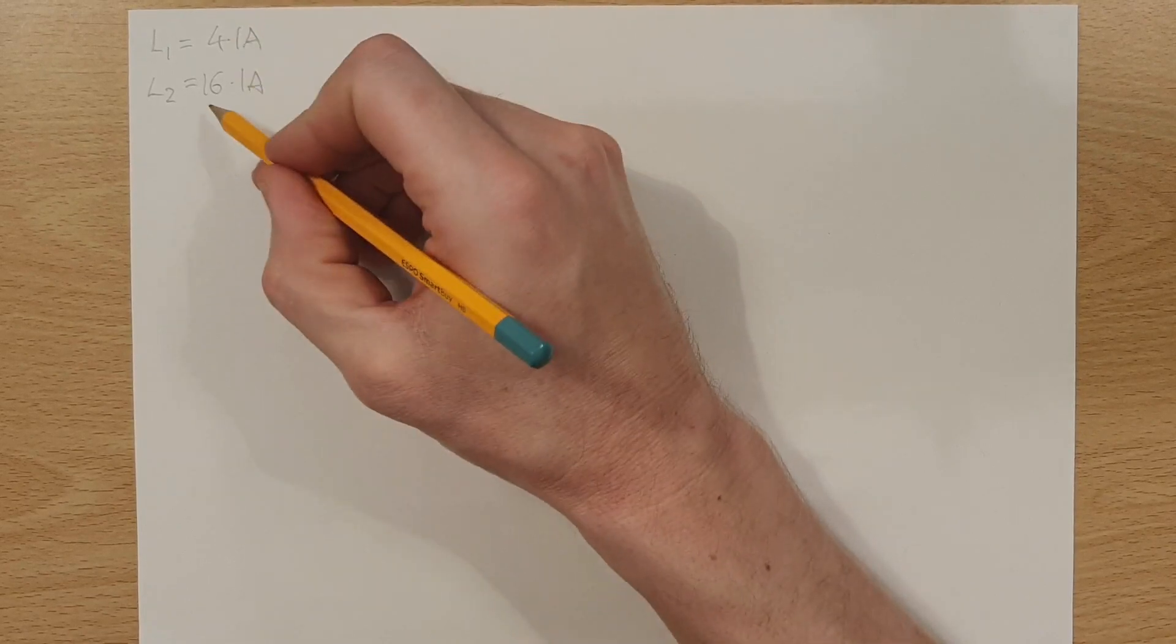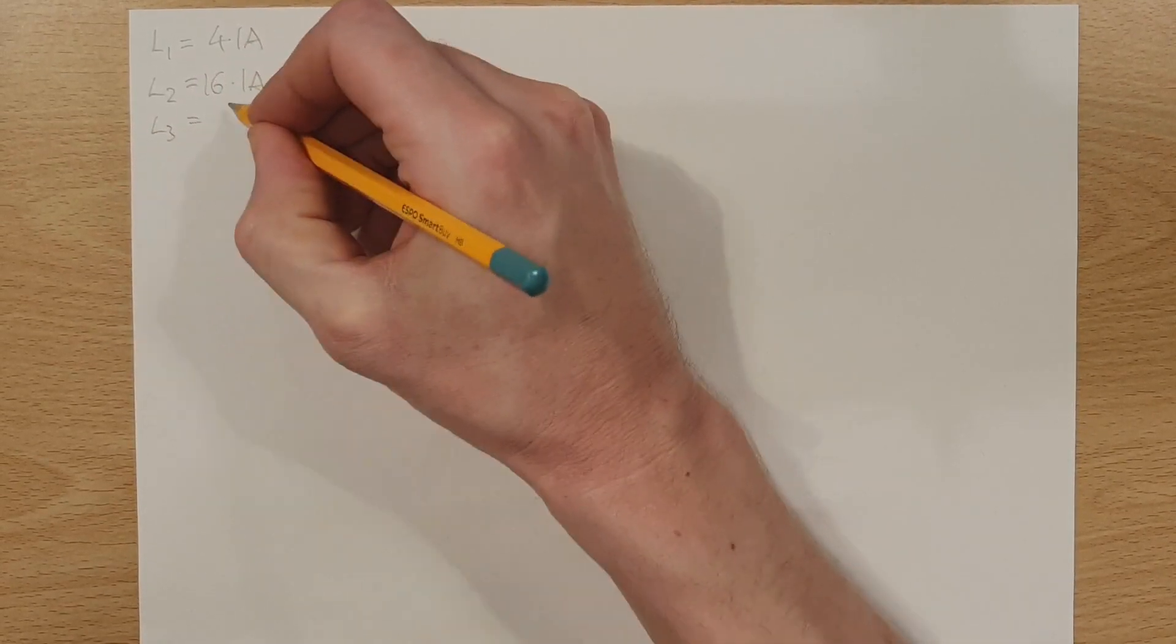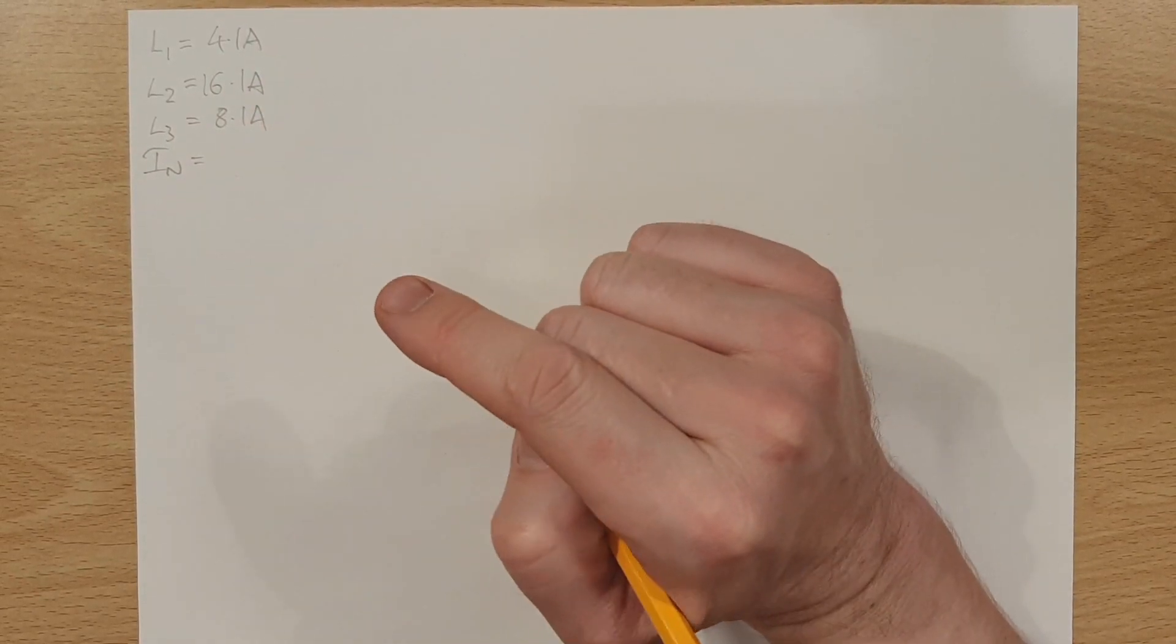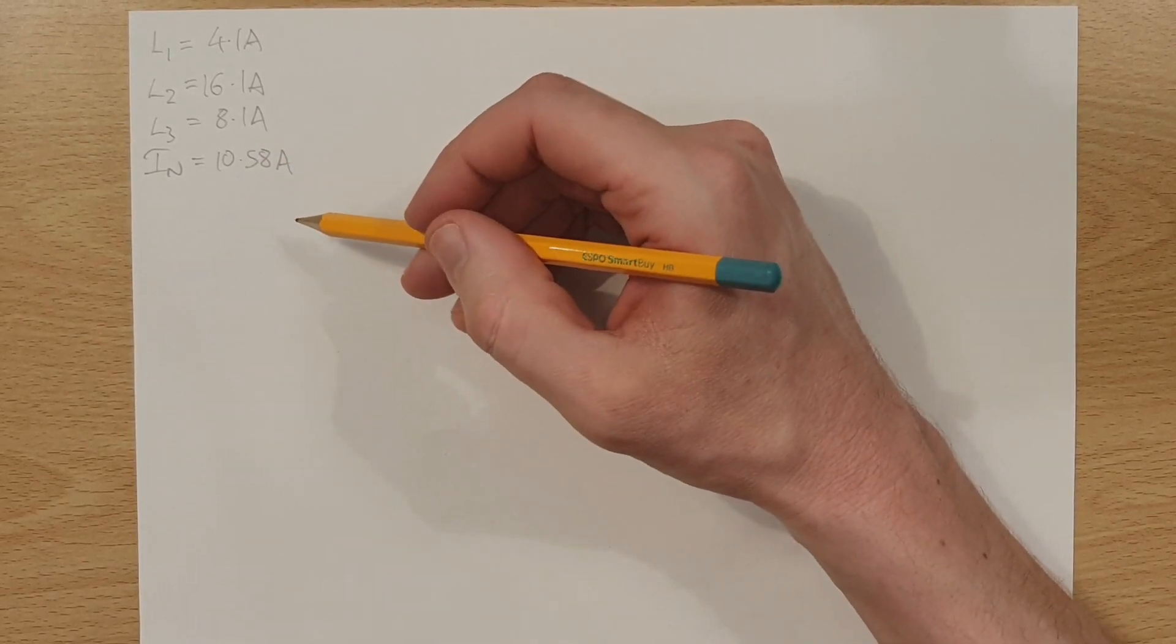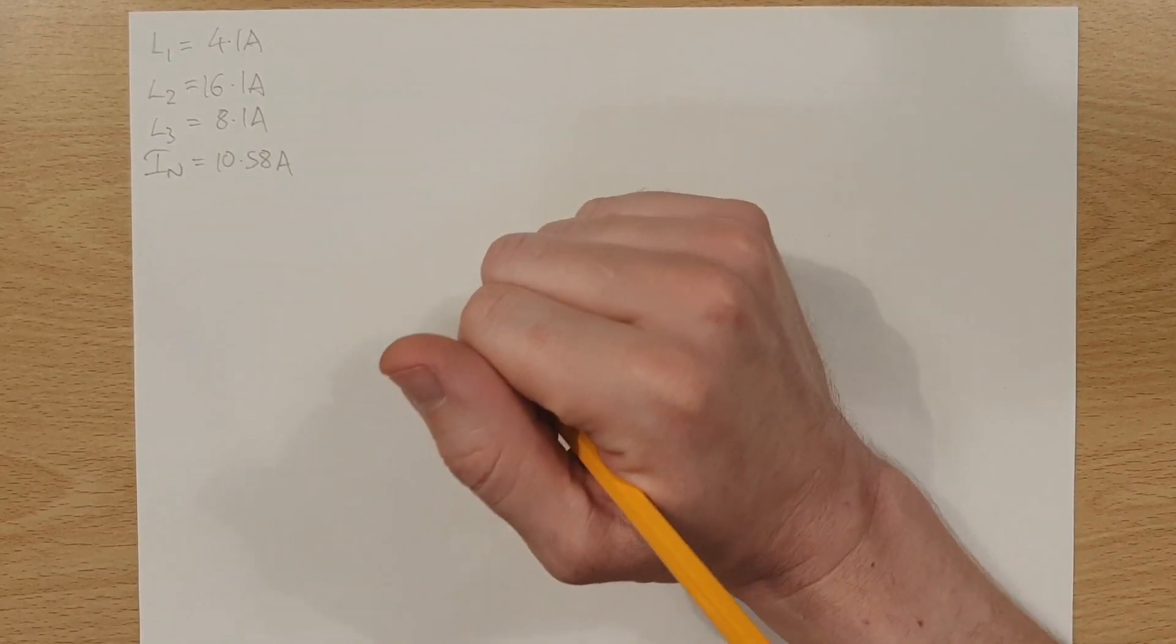In L2, we had 16.1 amperes flowing. And in L3, we had 8.1 amperes. And then finally, we measured the current in the neutral and that came out at a value. But then when we calculated it in the follow-up video, we saw that the value came out at 10.58 amperes. So we measured it slightly different to that. And then we calculated it. And we explained the reasons why those two values weren't exactly the same.